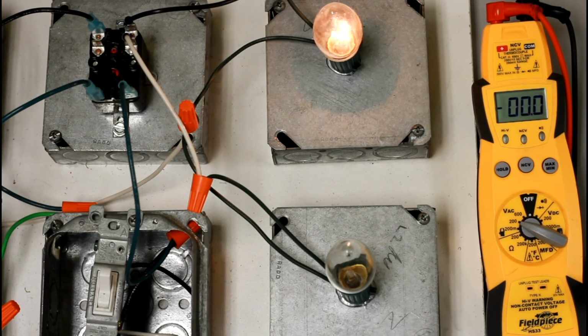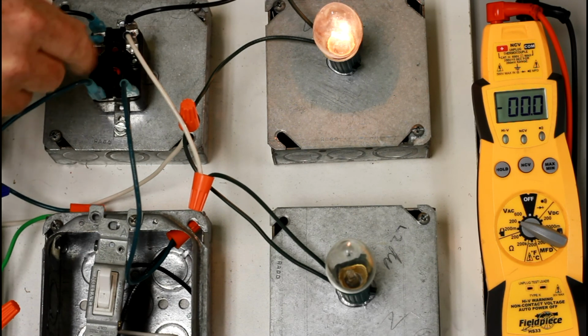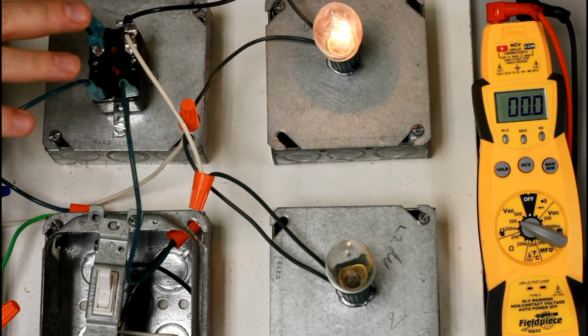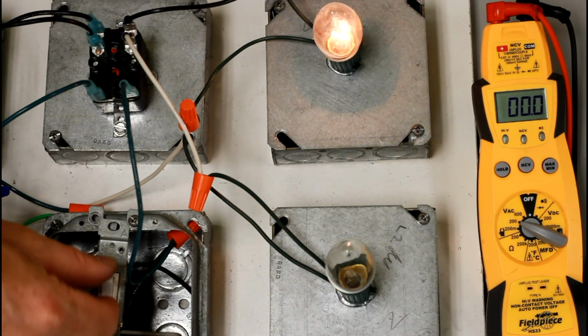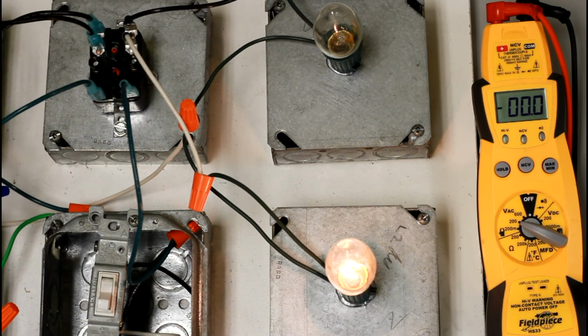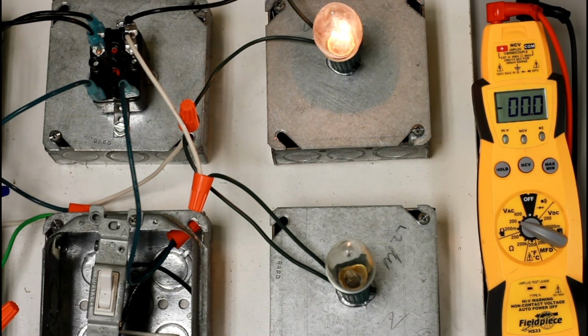Instead of having a double pole single throw, I'm going to change this to a single pole double throw. All I need to do is add a second power wire coming in so that both of these inputs have the exact same amount. Now, whenever I turn the switch on and off, it'll cause the lights to work like a single pole double throw switch. We have 1 input coming in, that's our 114 volts. Coming out, we have our normally closed and our normally open. To make those switch, we just turn the power on, so we send 24 volts to the coil.